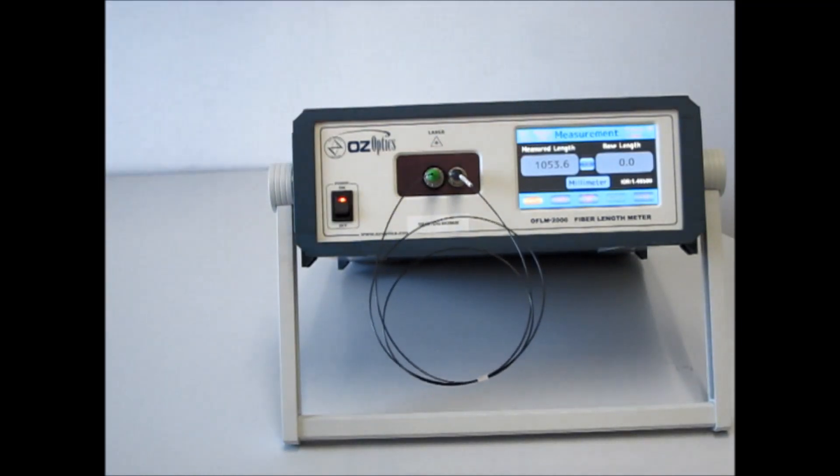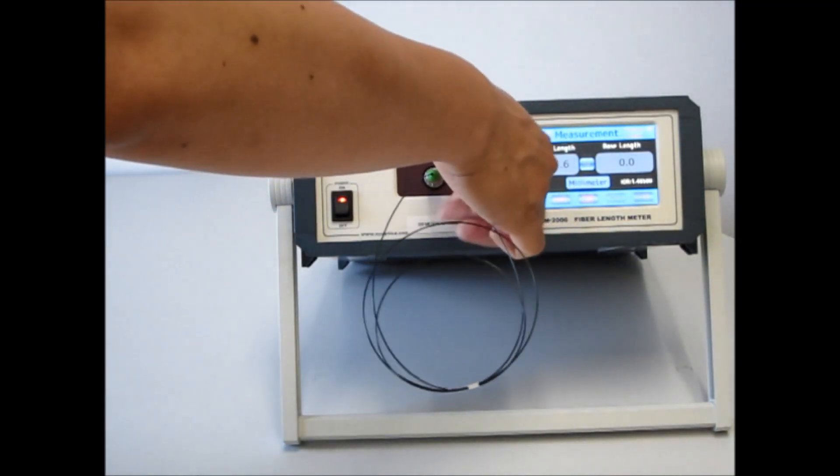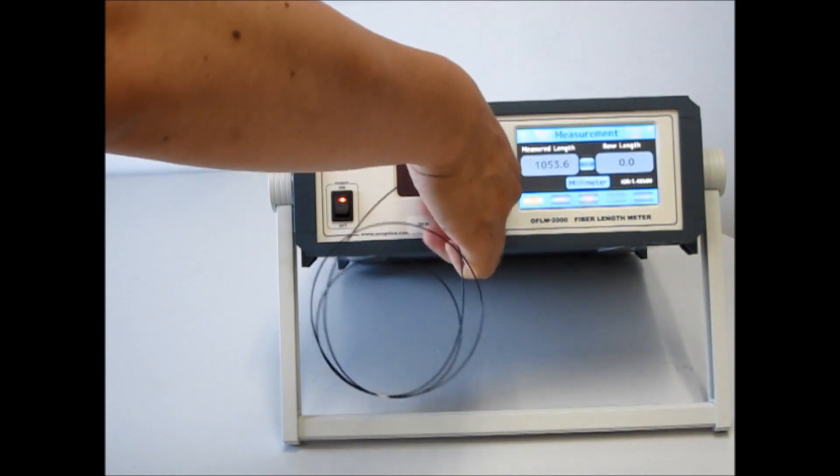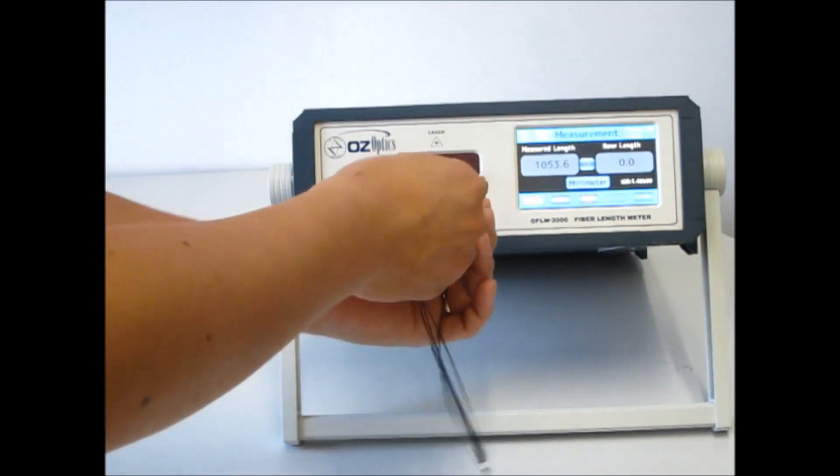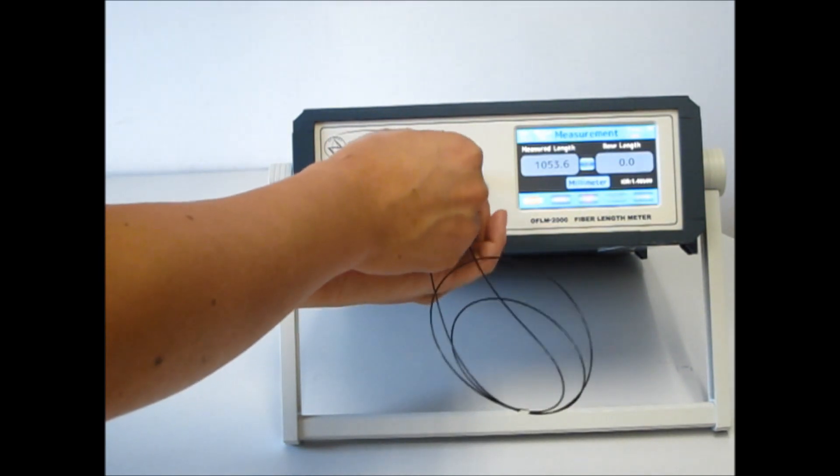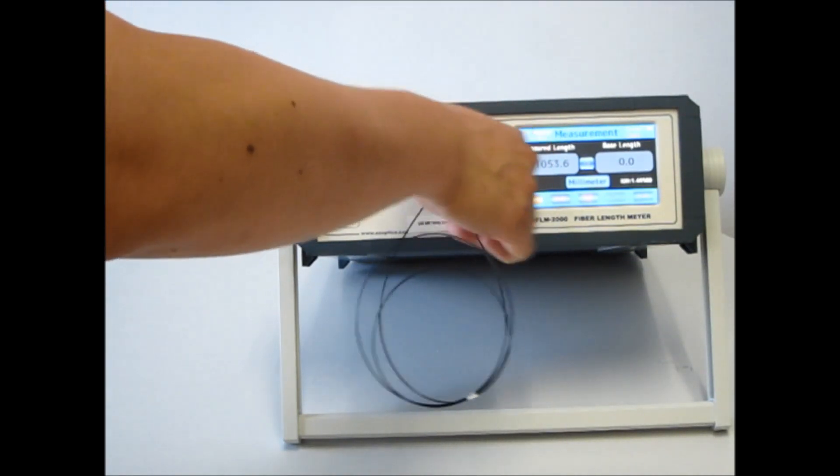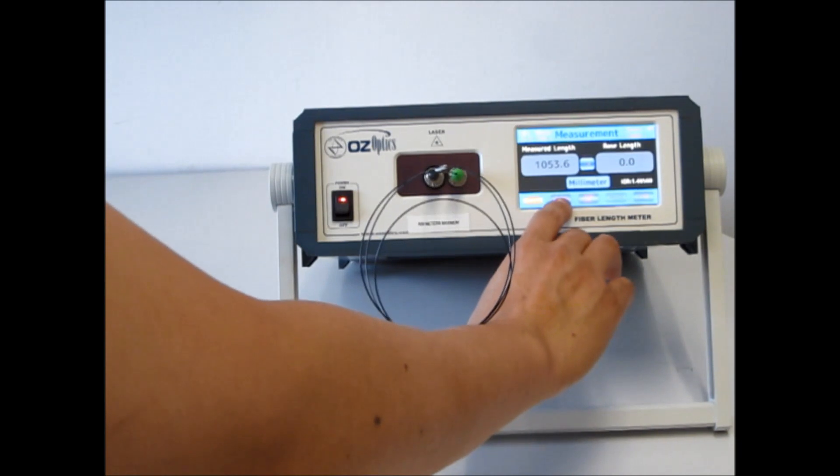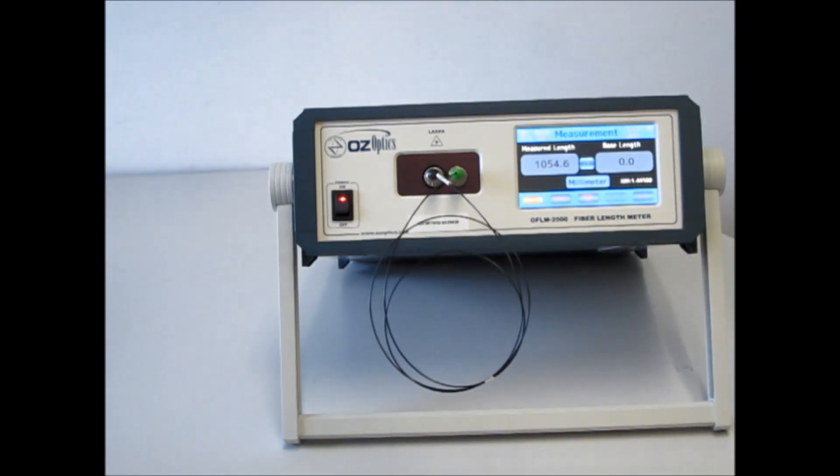Let's switch the ends to demonstrate the repeatability. You'll notice that the end with the green boot will be on the right, and the end with the black boot will be on the left. Tighten up the nuts and push the run button again. The measured length is 1,055 millimeters. The 1 millimeter difference is within measurement error.